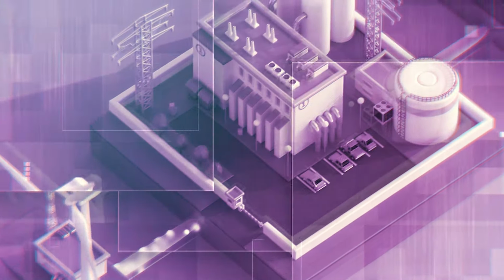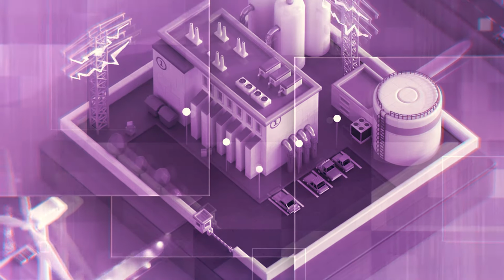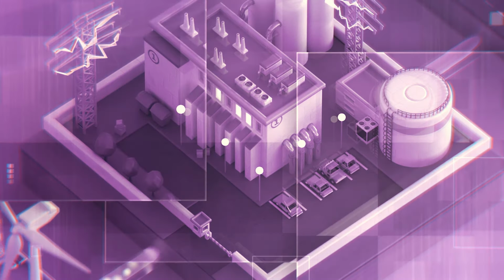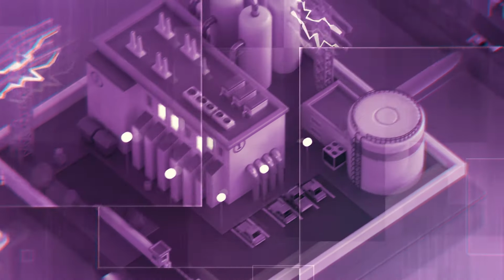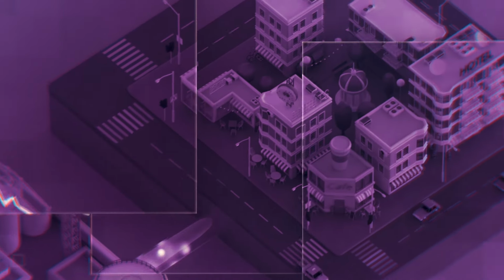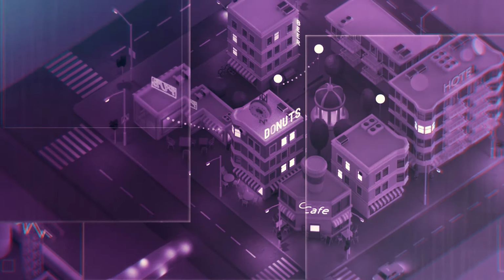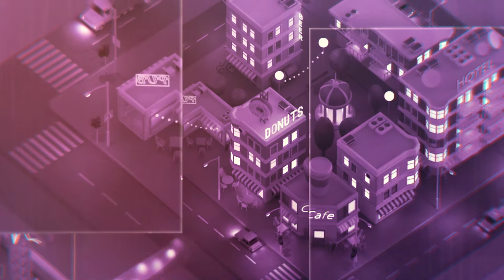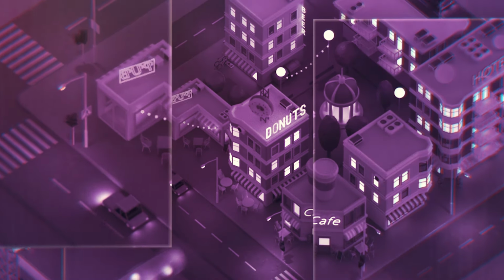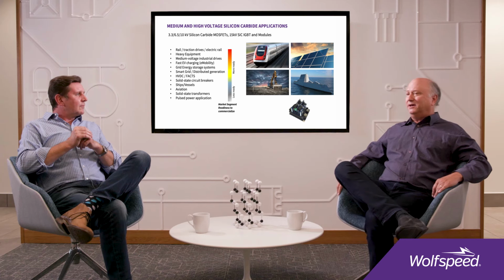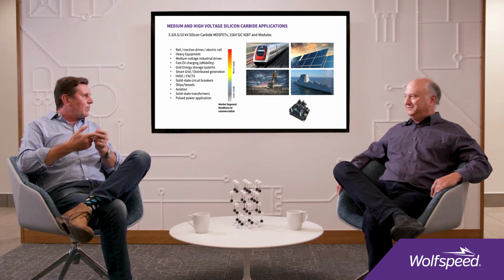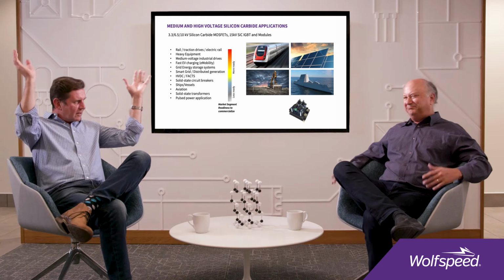What are we talking? The way I view it is typically 3.3 kilovolts and up. And in the case of silicon carbide, up goes much further than in the case of silicon. Silicon, in terms of IGBTs, goes up to about 6.5 kilovolts. Thyristors may go up to 10 kilovolts, but they have to be cooled very heavily - this is like static VAR compensation and the big power management things.